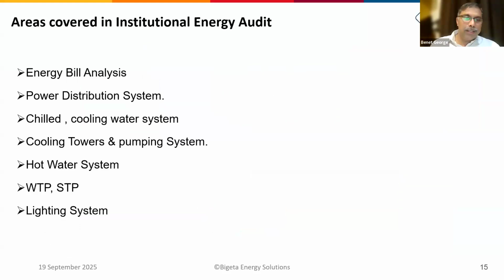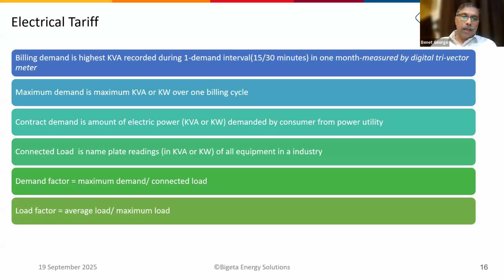So these are the typical areas to be covered: energy bill analysis, especially electricity bill analysis, power distribution system, chiller and cooling water system, cooling towers, pumping system, hot water system, WTP, STP, lighting system. In addition to this, maybe UPSs, AHUs, or other equipment if there is any. When we analyzed the earlier slides, we saw that we need many instruments, but to identify cost saving opportunities, you can start with analyzing your electricity bill itself. In the electricity bill, you will get maximum demand, energy consumption, power factor, in some cases the demand factor or load factor, based on the state. So this will give some of the opportunities.